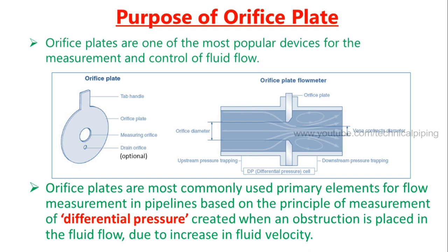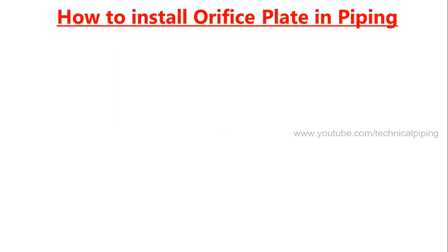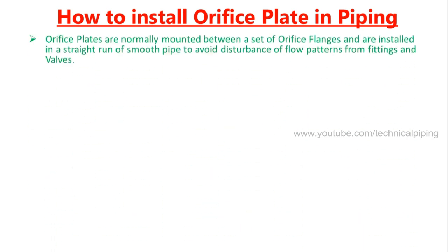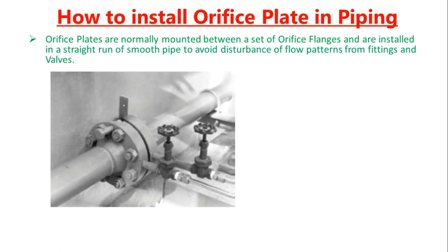Due to the increase in fluid velocity, let's talk about how to install an orifice plate in a piping system. Orifice plates are normally mounted between a set of orifice flanges and installed in a straight run of smooth pipe to avoid disturbance of flow patterns from fittings and valves.